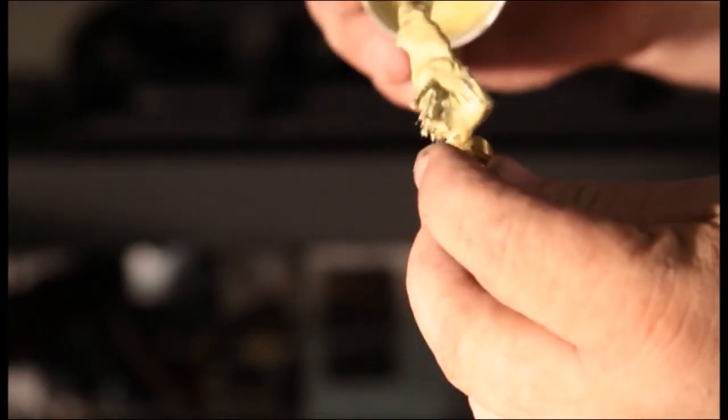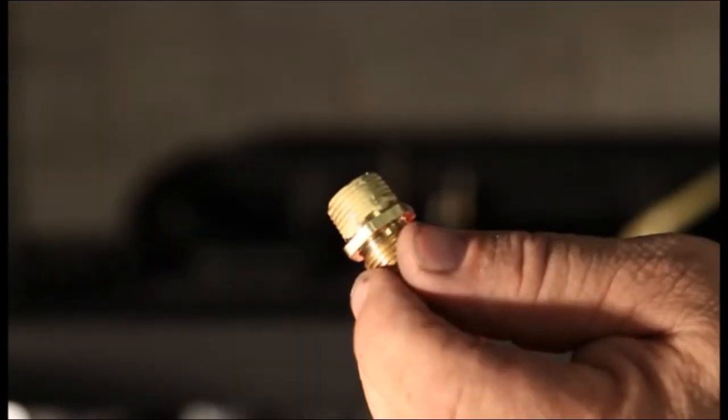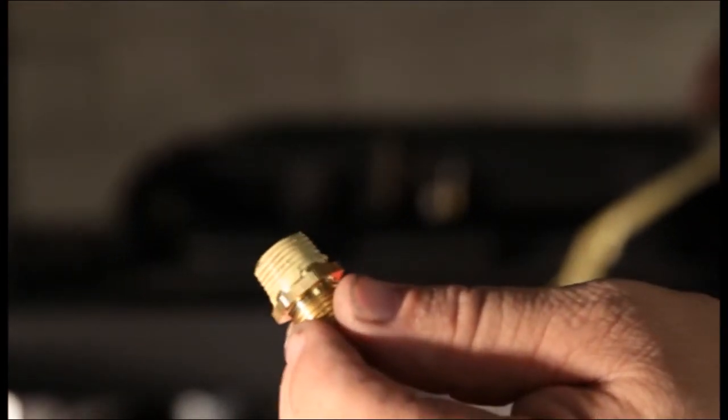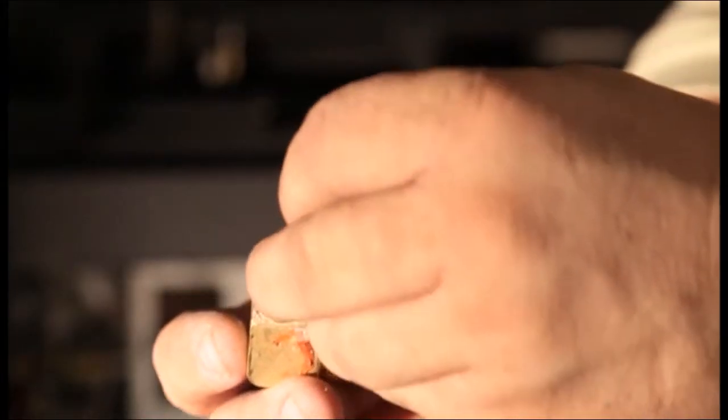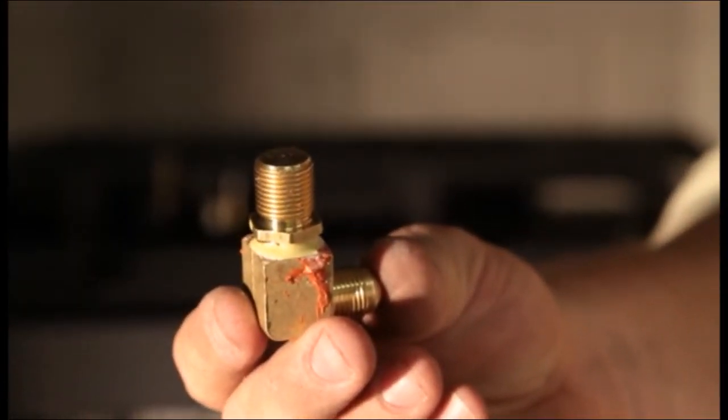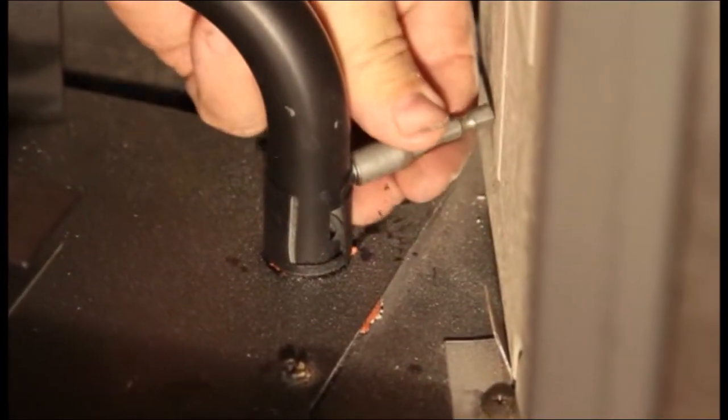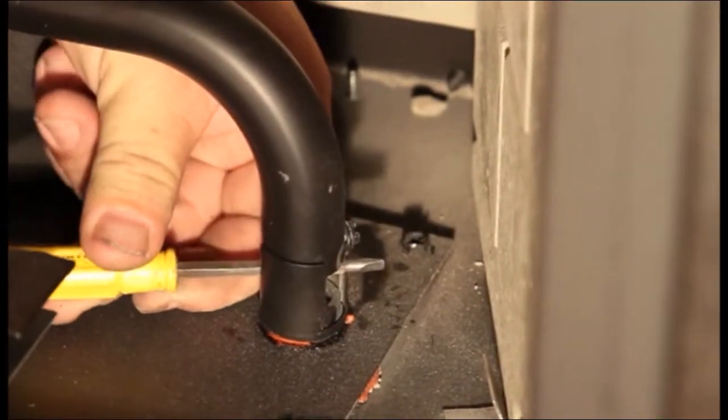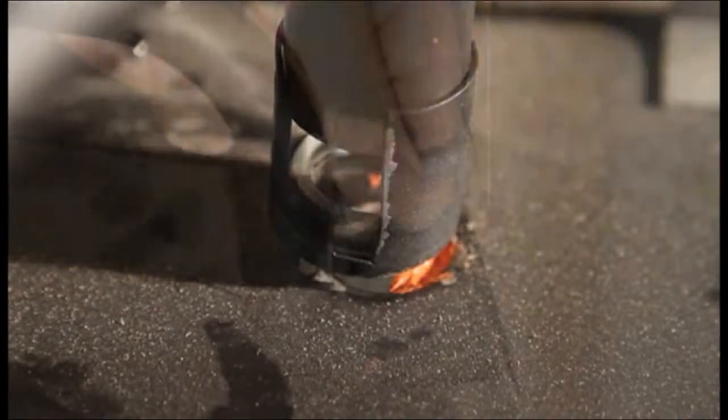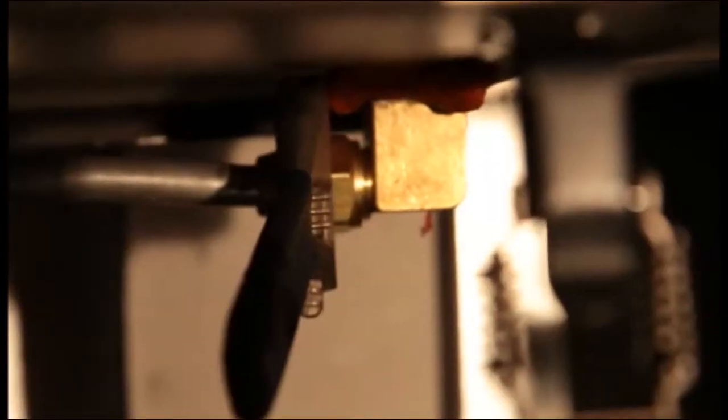Apply a light amount of thread sealant to the bottom threads of the LP orifice. Replace the new LP orifice to the brass elbow. Adjust the air shutter to fully open. Reinstall in reverse order.